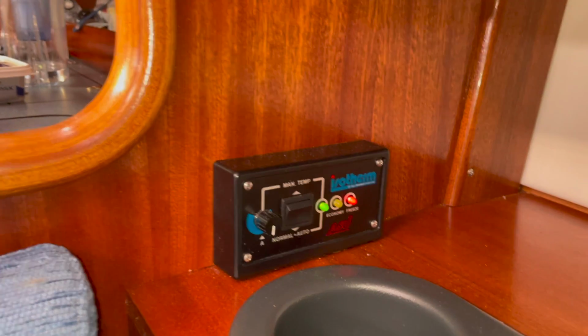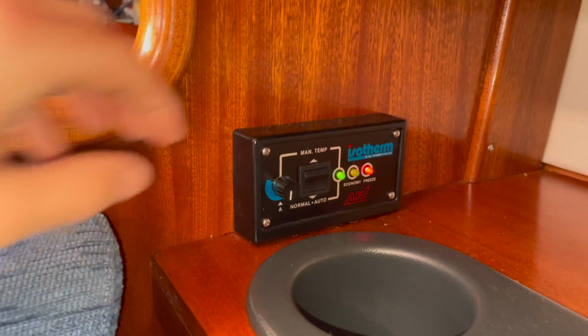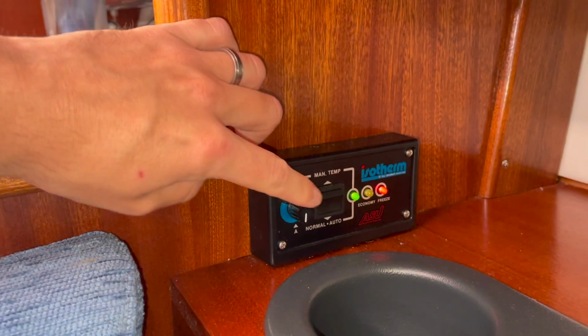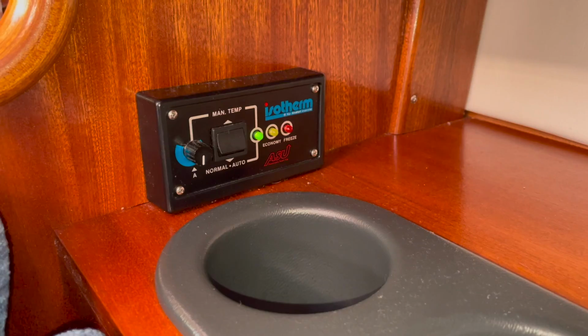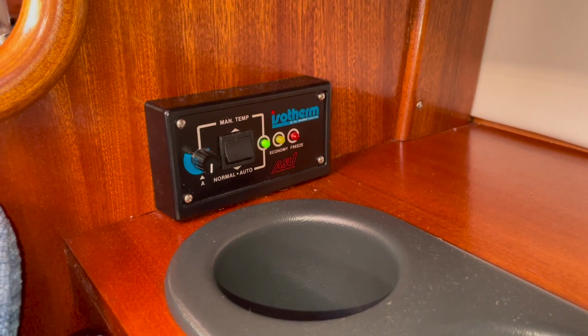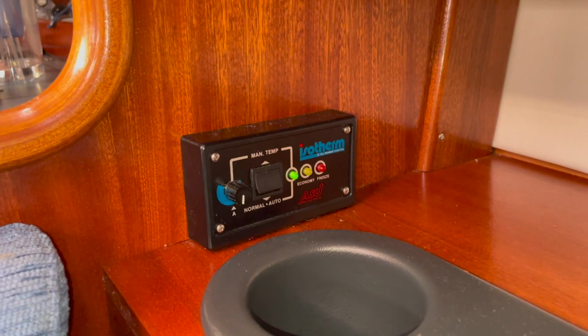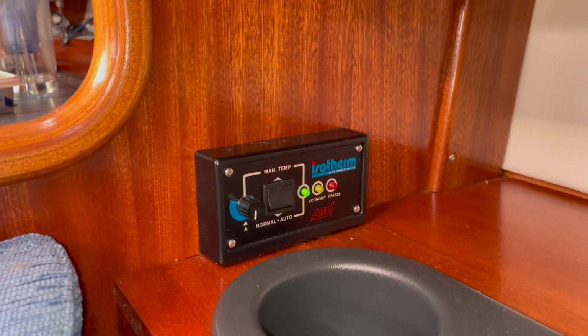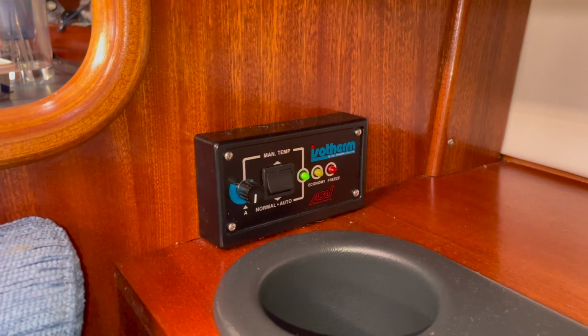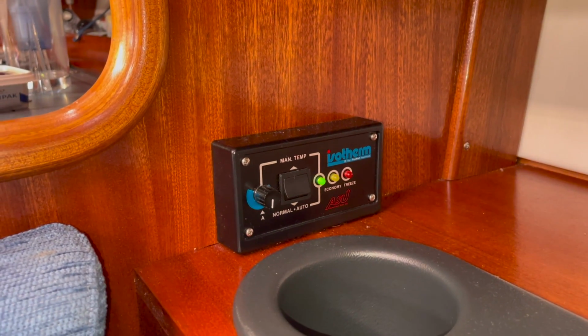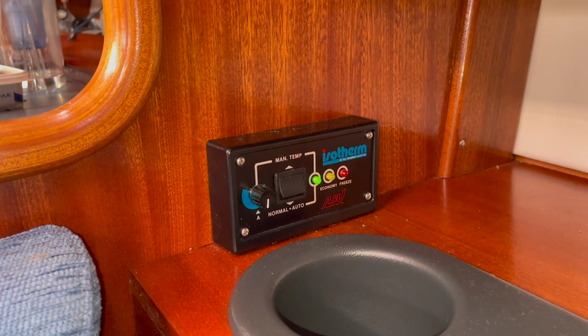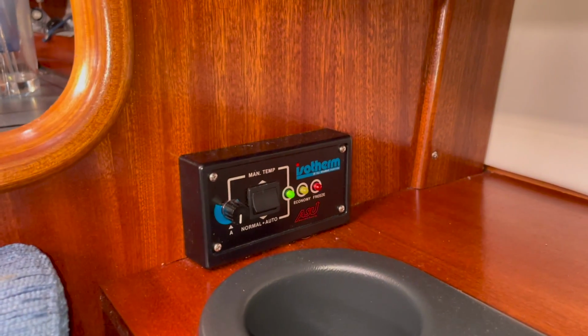That doesn't like that because it keeps clicking on and off all the time, so I'm going to switch that to manual, and that will stop it coming on and off because it's not happy. It's starting and then it's stopping. I guess it's just pulling the voltage down just a little bit too much for the unit to understand what's going on. So we'll stick that on manual for now, and stop that switching on and off every 5 seconds.